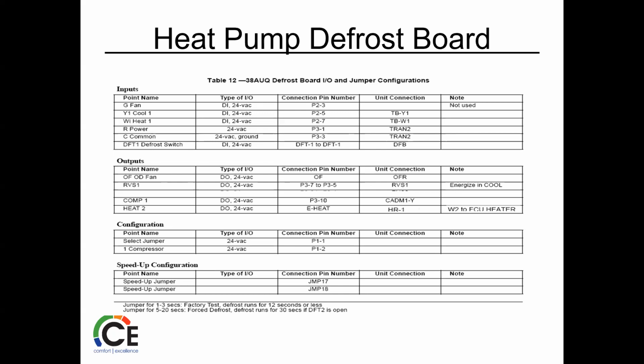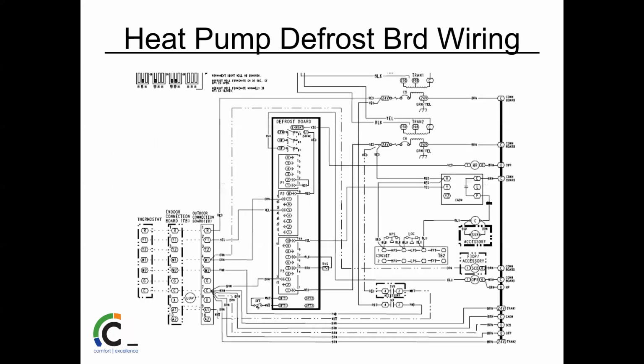Outputs, inputs, configurations. I think I'm going to spend a whole lot of time in there. And then the speed up jumper on some of these. So basic wiring here. Again, just remember that once we add something here like a defrost board or an IGC, it starts to take over control of the unit in select modes. And a lot of times it really just takes over the fan. When the fan comes on, when it goes off, it starts to operate that, where other units, the main board does it.